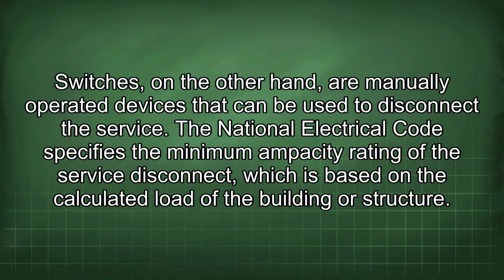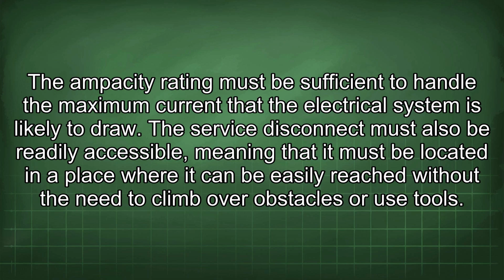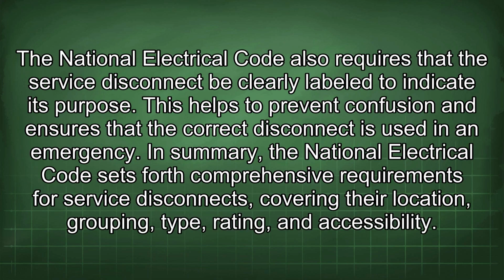The National Electrical Code specifies the minimum ampacity rating of the service disconnect, which is based on the calculated load of the building or structure. The ampacity rating must be sufficient to handle the maximum current that the electrical system is likely to draw. The service disconnect must also be readily accessible, meaning that it must be located in a place where it can be easily reached without the need to climb over obstacles or use tools. The National Electrical Code also requires that the service disconnect be clearly labeled to indicate its purpose. This helps to prevent confusion and ensures that the correct disconnect is used in an emergency.